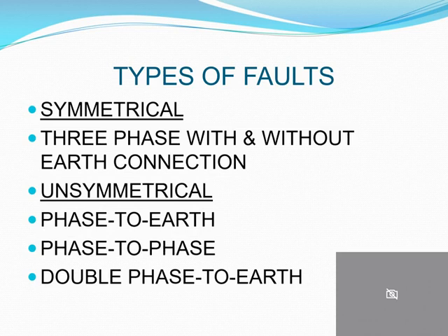As our electrical networks are usually three-phase systems that we deal with, we're going to be looking into two types of faults that can happen in those systems. The first one is what we call a symmetrical fault. And this means that all three phases, either they have an earth or not, but you will have a fault on all three of your phases in your system.